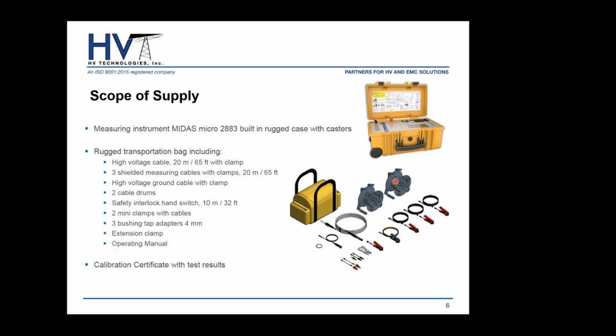The safety interlock hand switch is standard with the supply of the instrument in the transportation bag. You also have mini clamps for maybe smaller DUT and adapters for bushing taps, if you're interested in doing bushing testing. You will, of course, get an operating manual and certificate of calibration, and the extension clamp is also provided in order to increase the opening of your clamps, so you can maybe fit over larger transformer bushings or larger terminals.